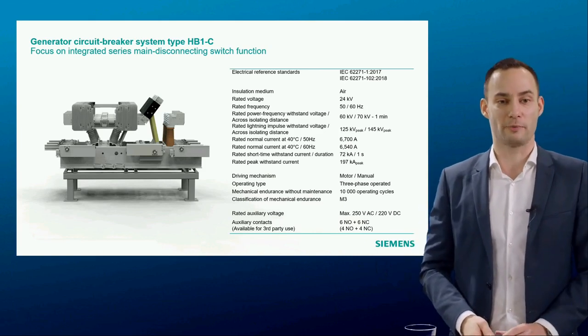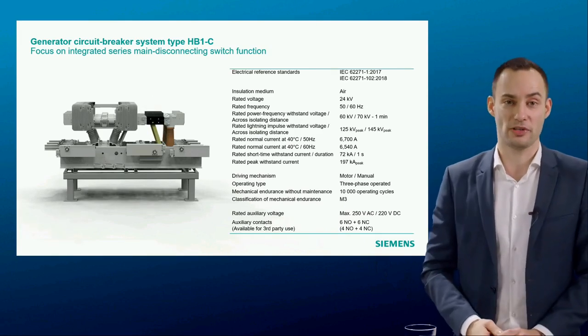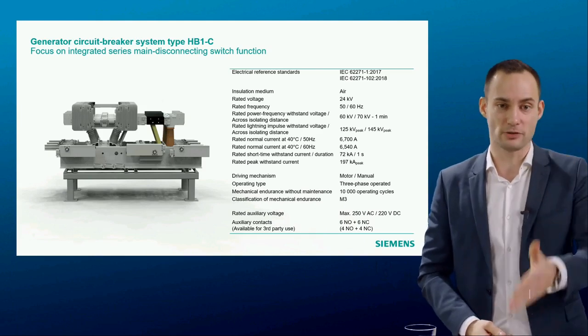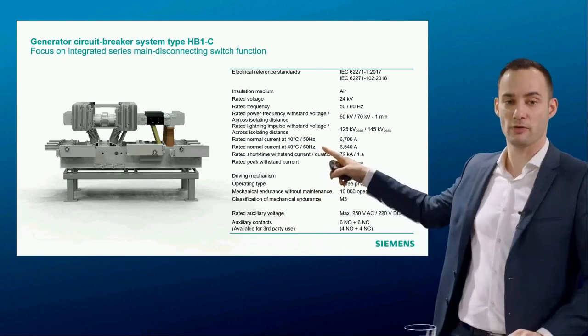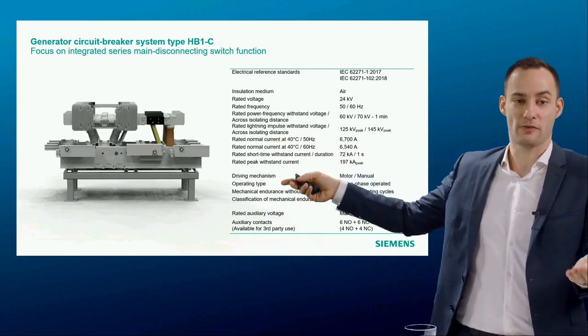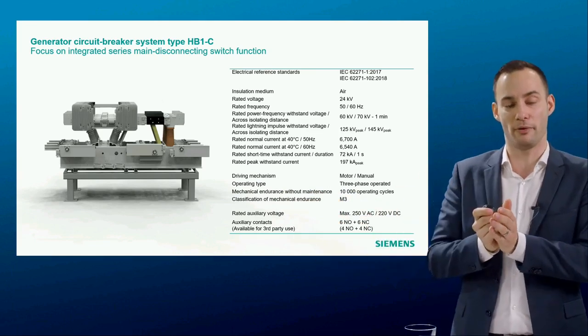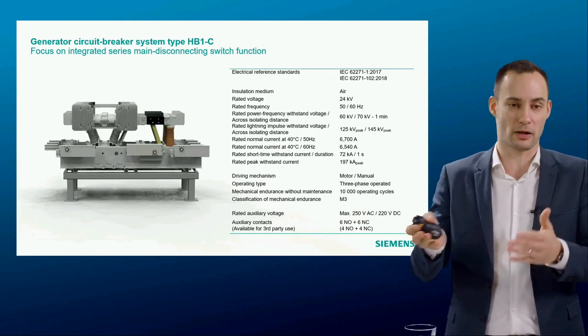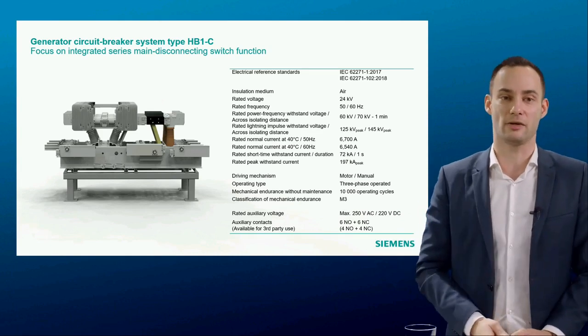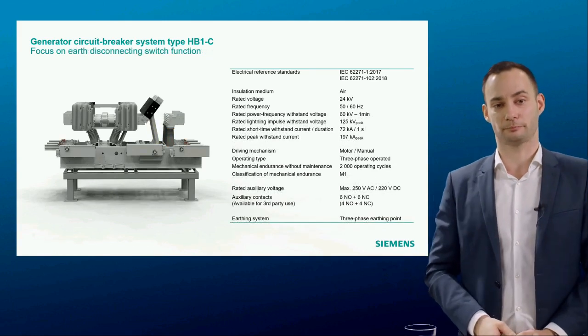And just to also explain quickly how it closes. In that case, here you have the disconnector in closed position. And whenever you want to do some maintenance or whenever you want to have this visual opening of the main current path, because on one side is a terminal, on the other side also, as you can see here, I cannot say whether my GCB, my arcing contact in my vacuum bottle, are open or not. Could be they are open, could be they are closed. Visually, from this location, I cannot say. A good way to say it is to open the disconnector.